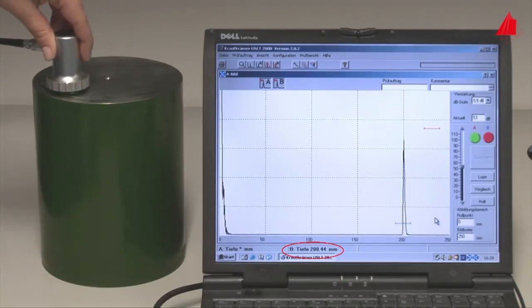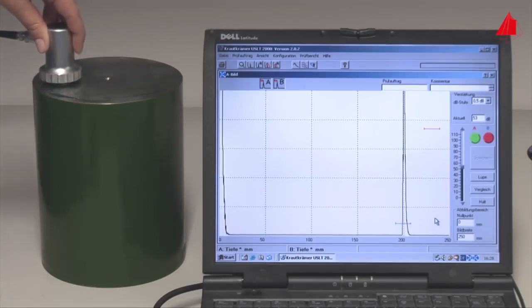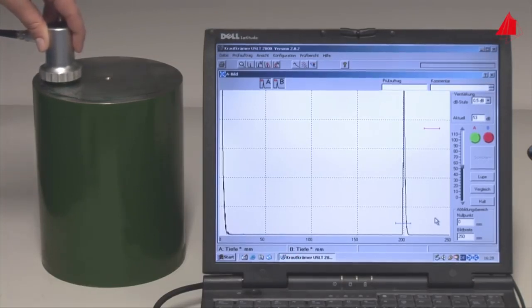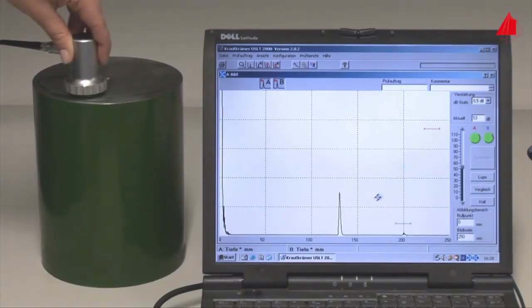And here we go. The material tester scans the upper front end of the cylinder with a probe and observes the monitor. A defect echo appears on the monitor. This defect is located in a depth of 130 millimeters below the surface.